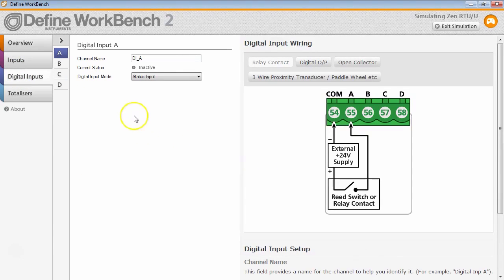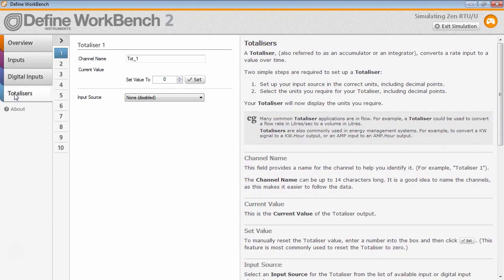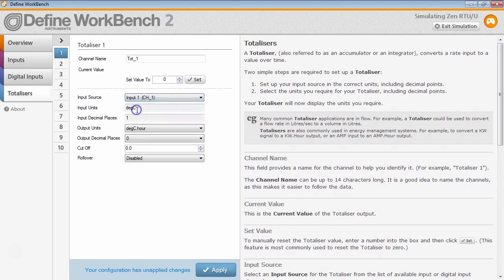Digital inputs are similar. You can select either the digital input as just a pure status input, or you can select counter, frequency, or flow modes, or RPM, and so on. Each of the digital inputs is isolated, and you will need to power each of the digital inputs through this supply. Totalizers: if you are using a flow application, you might want to use the totalizers to calculate how much total flow has been through. Again, select the source input channel for each totalizer, and select the parameters here for the totalizer.